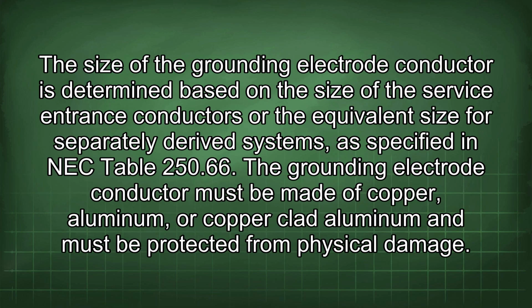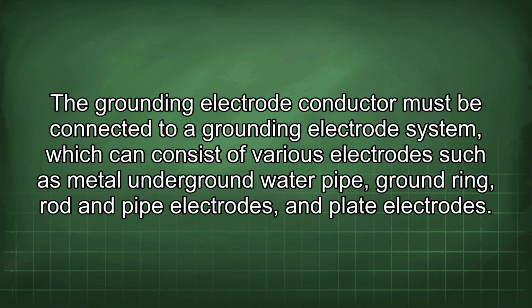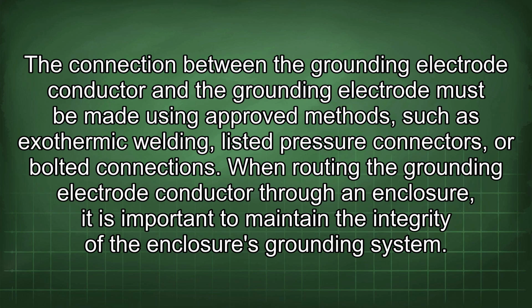The size of the grounding electrode conductor is determined based on the size of the service entrance conductors or the equivalent size for separately derived systems, as specified in NEC Table 250.66. The grounding electrode conductor must be made of copper, aluminum, or copper-clad aluminum and must be protected from physical damage. The grounding electrode conductor must be connected to a grounding electrode system, which can consist of various electrodes such as metal underground water pipe, ground ring, rod and pipe electrodes, and plate electrodes. The connection between the grounding electrode conductor and the grounding electrode must be made using approved methods such as exothermic welding, listed pressure connectors, or bolted connections.